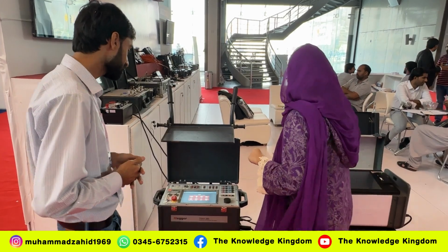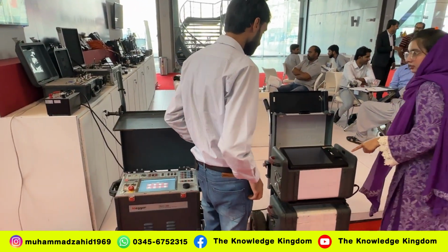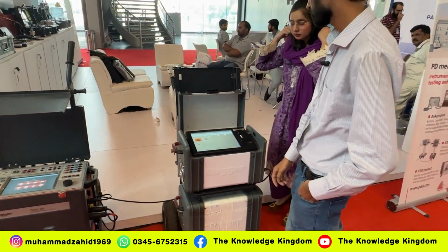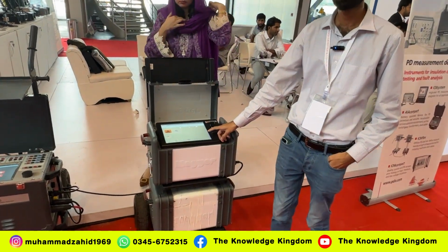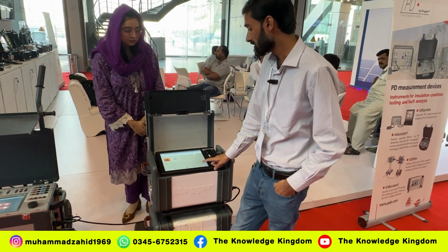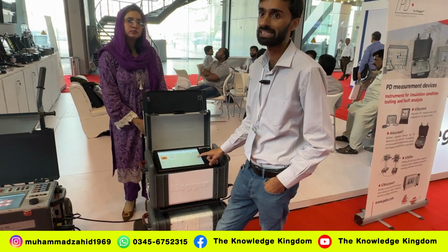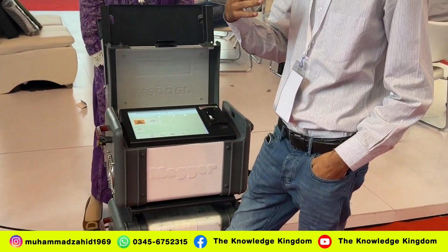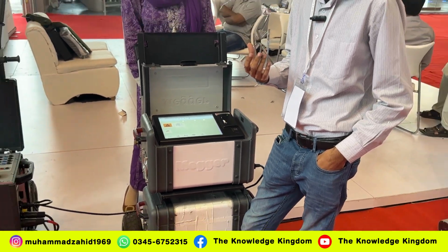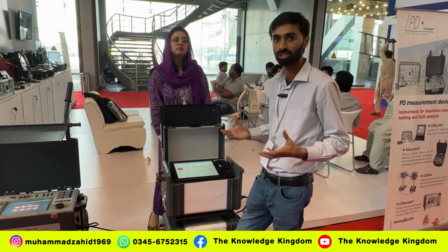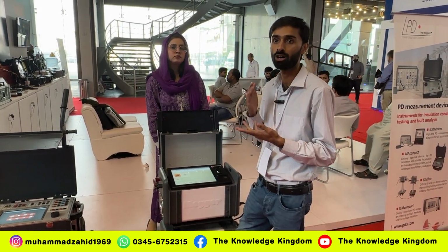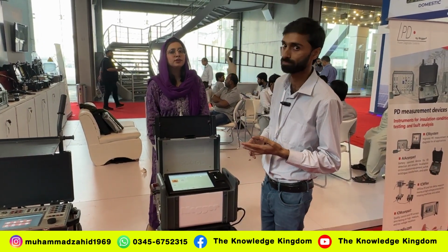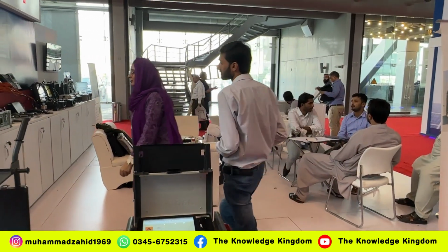Okay, so let's move ahead, please. All right. This equipment is functioning? Yes, it is also functioning. It is called the Delta 4000 and it does the testing of the transformer. It does test the insulation, the condition of insulation in the transformer. So it checks the overall condition of insulation which involves the tank, the oil and the winding of the transformer. Okay, let's move ahead.